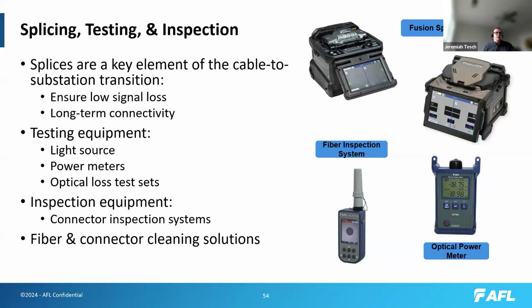It's actually recommended when you receive a cable from a manufacturer to do that testing, to make sure it's testing as it did at the plant, that there was no damage during shipping, and to do that again before installation.